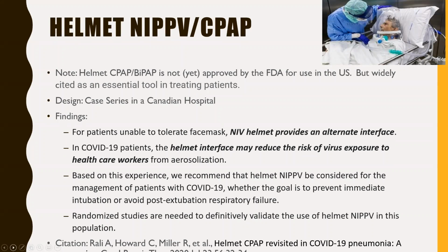You're containing it, and the exhalation port has a filter, but the patient may still be coughing and lifting up the mask and things along those lines. If they actually have a helmet on, there's less risk of that sort of stuff. They could still theoretically try to pull the helmet off, but it's much more difficult than simply taking off a full face mask or nasal pillows or whatever.